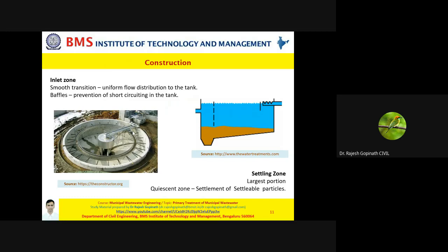So baffles are very important in your inlet zone to prevent short circuiting from taking place, because in case you have overload, if you have a shock load, and if short circuiting takes place, then all the suspensions, all the settled solids, get resuspended. So therefore, the process of settling and sedimenting is disturbed. So the inlet zone is very important when it comes to the operation of your sedimentation tank.